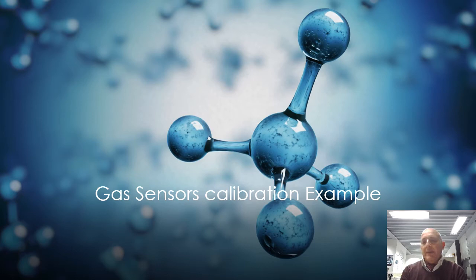Of course, that particular behavior is shown by all the sensors of that class that we have analyzed. So our correction method applied to all the sensors, not exactly with the same parameters, of course, but that method can be applied to all the PMS 7003 sensors and also beyond. Whenever an optical particle counter gives you an estimation of the concentration, you can apply that kind of approach.